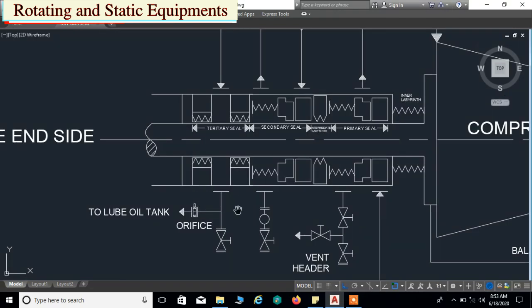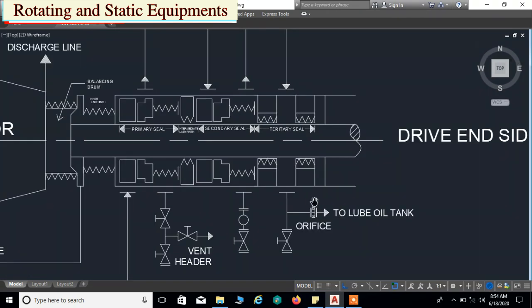The instrument air return lines from the tertiary seal chambers are sent directly to the main lube oil tank, because next to the tertiary seal the bearing units are located. Instrument air acts as a barrier against lube oil and lube oil vapors coming from the bearing units, preventing them from entering the mechanical gas seals. It carries the lube oil and lube oil vapors draining from the bearing units and discharges them into the main lube oil tank.